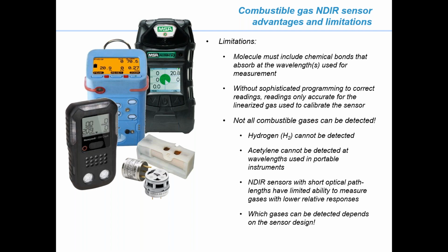NDIR sensors with short optical paths, well, the benefit there is they use virtually no power. However, they are unable to measure gases that have lower relative responses to IR sensors, and they can be wildly inaccurate even for the gases they are designed to measure.